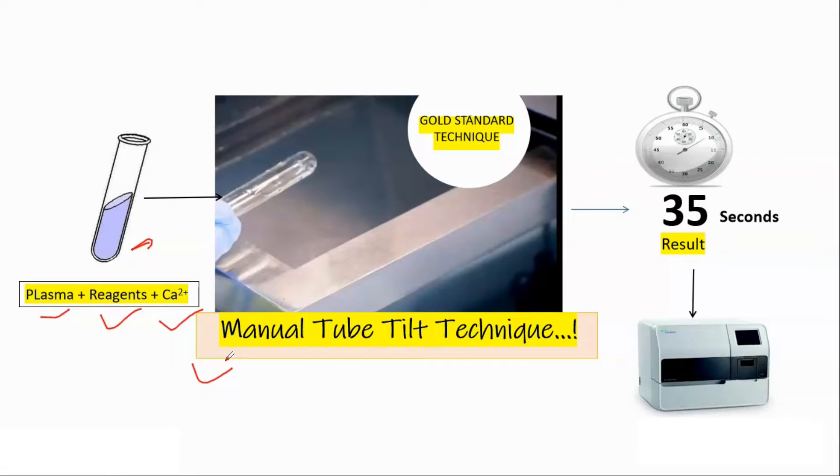Then we again dip in the water bath and again take out and look for the clot. So as soon as clot is visible to the person performing the test we get our result time, that is 35 seconds, 20 seconds, whatever the test or result.